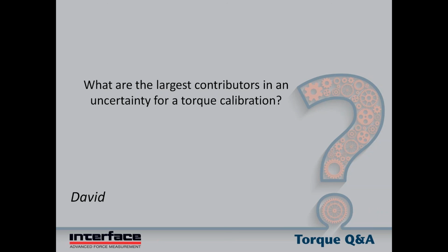The problem here is that the bubble level is typically applied at the center line of the device under test, and this ignores the fact that the moment arm itself can deflect over its length. It can be level at the center of rotation of the torque sensor, but as it moves outboard on the cal arm, that deflection needs to be monitored as well. So big error potentially is a moment arm that doesn't have adequate stiffness to prevent deflection over its length.